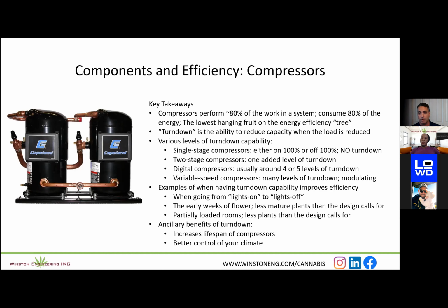Then you have a two-stage compressor, which just adds one level of turn down from that single stage. So call it 50%. Where you really want to be in this industry is at least some level of a digital compressor or variable speed compressors. Digital compressors will stage usually about 4 to 5 levels to get the full capacity. Variable speed compressors, I don't want to say infinite modulation, but you can effectively dial that into exactly where you want it. And your control systems can ramp these things up and down so that you can effectively match load with capacity. That's the goal: matching your load with capacity.